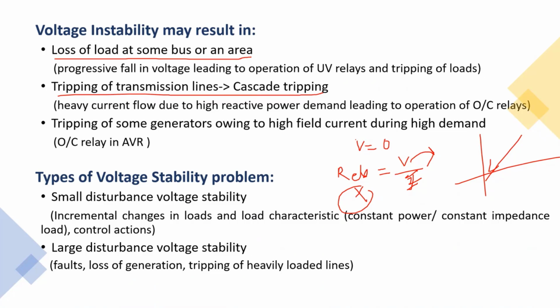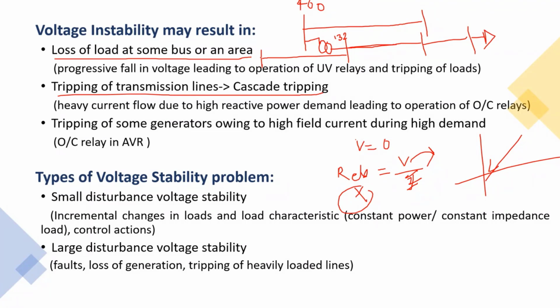When there is a voltage collapse, we have seen this, so let me share one example. There is a 400 kV transmission line. It was a long transmission line like this, 400 kV, and there you have a 132 kV transmission system. Let me create this. This is 400 and this is 132 kV. This is a northeast example. And this was feeding a kind of radial load in the system. And it is connected here at 132 kV itself. However, you have a very good voltage source. This is a generating plant.